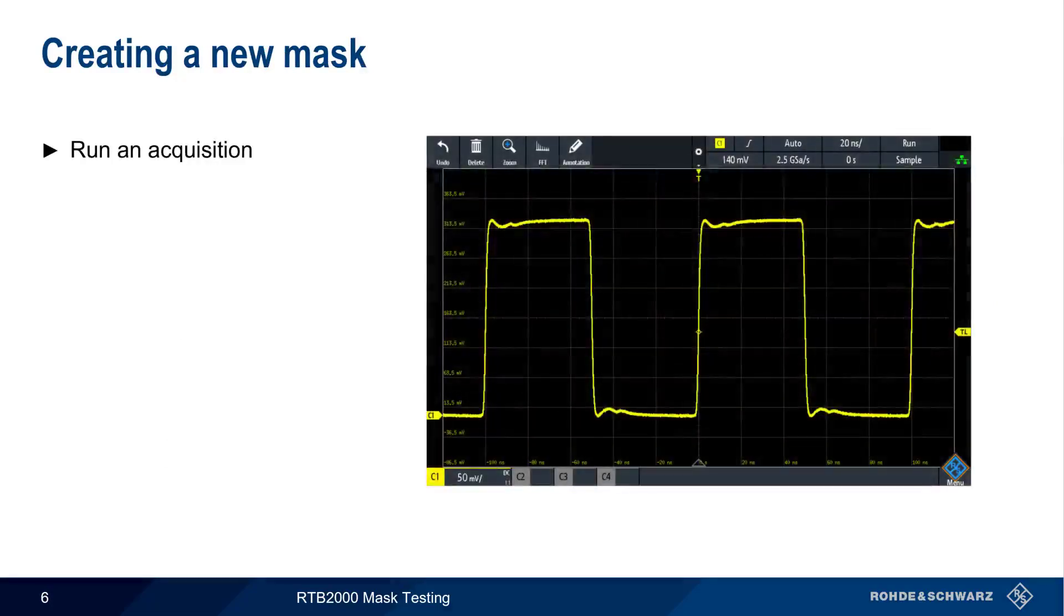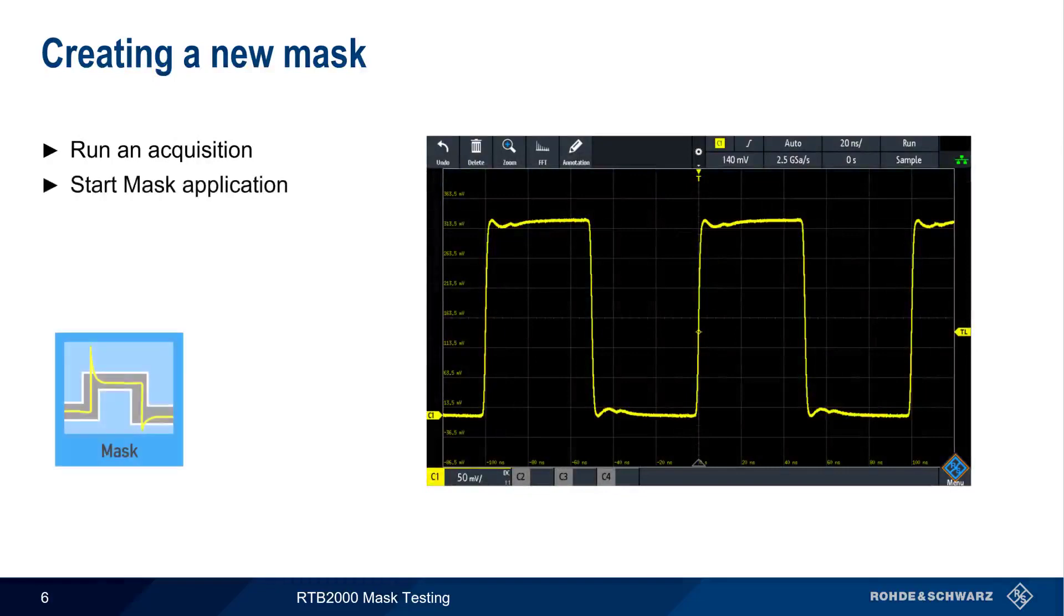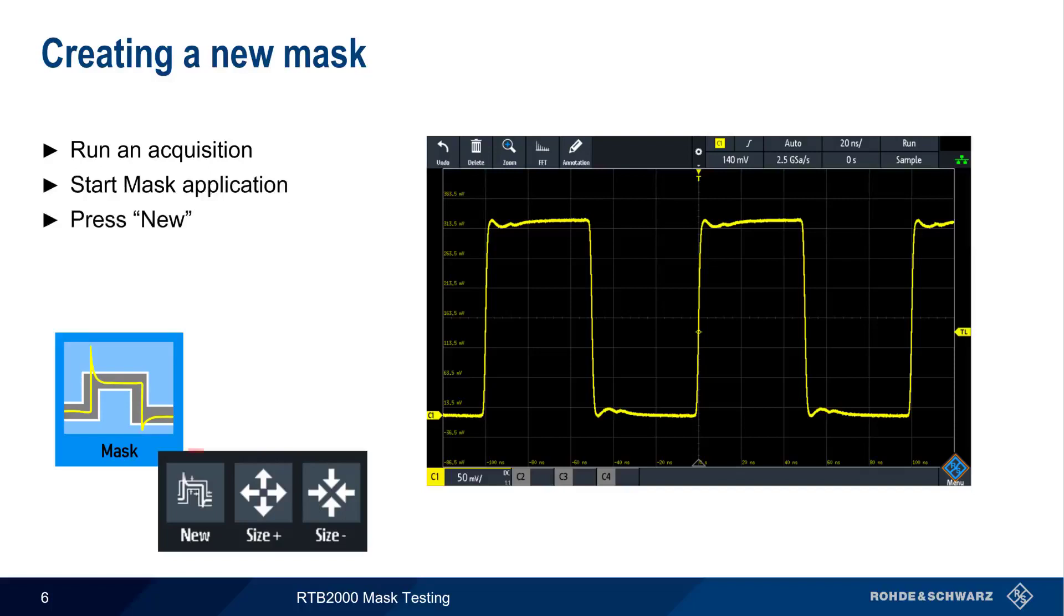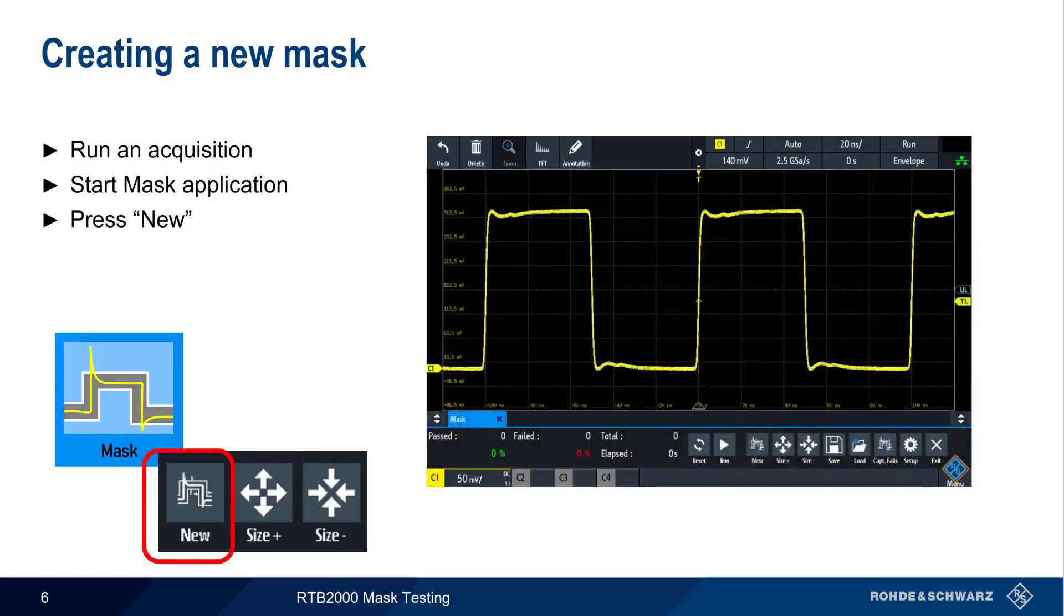Let's start with creating a new mask. Masks are created from acquired waveforms, so the first thing we need to do is start an acquisition. The next step is to start the mask application and press New. A relatively tight mask will then be created around the acquired waveform. This may be difficult to see unless you zoom in or look very closely.